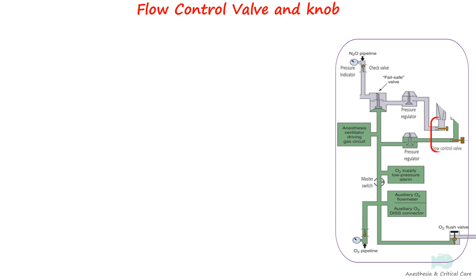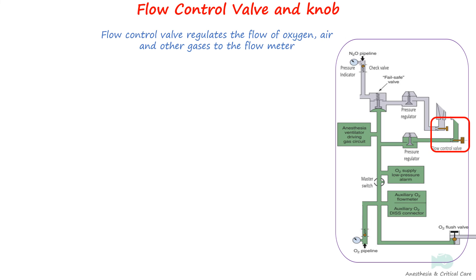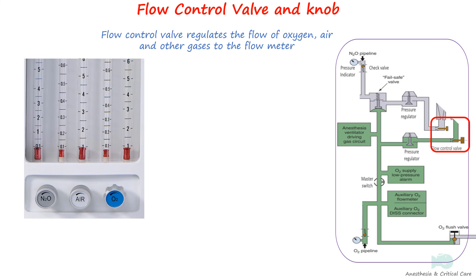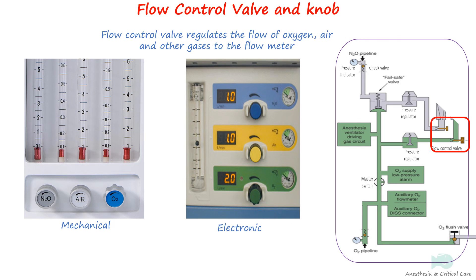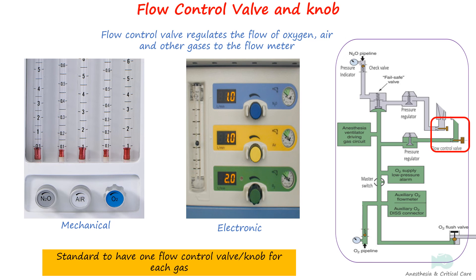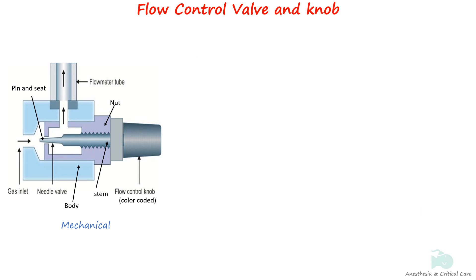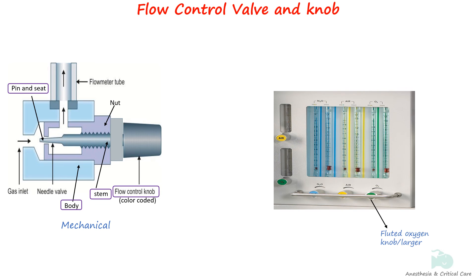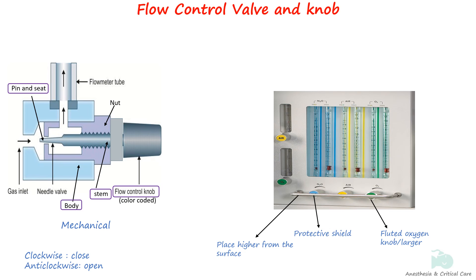The flow control valve regulates the flow of oxygen, air, and other gases to the flow meter or indicators, and can be either mechanical or electronic. Current standard requires one flow control for each gas, adjacent to or identifiable with its flow indicator. The mechanical flow control valve consists of a body, stem, and seat; the stem is connected to the flow control knob. The oxygen flow control knob is larger and fluted compared to others, which are rounded. These knobs are sometimes protected behind a shield to minimize accidental changes in position, and are placed high above the working surface.